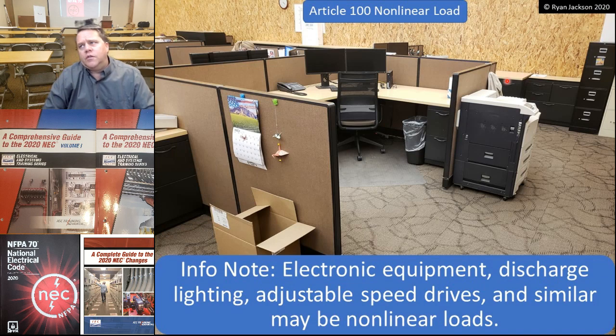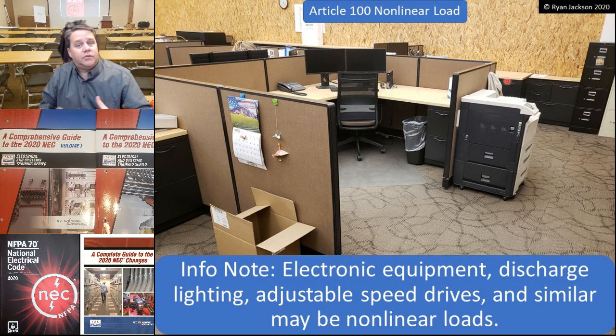There's an informational note that's a bit more useful than the definition, really, and it tells us examples of nonlinear loads. Electronic equipment, electric discharge lighting, adjustable speed drives, and similar may be nonlinear loads. This is becoming a bit less of a problem now than it was, say, 20 years ago, because we're able to mitigate the effects of harmonic current nonlinear loads by using capacitors and different things. But laser printers, lighting, pretty much anything you see in an office building, these things are all nonlinear loads.